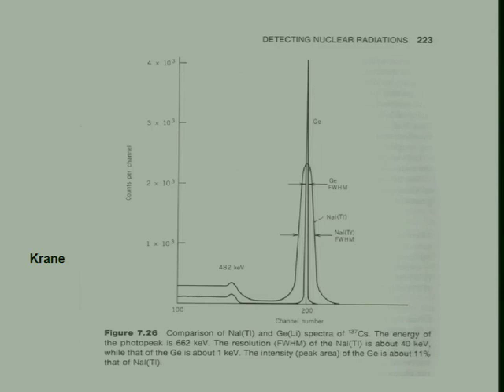And so it's the full width at half maximum there. And for sodium iodide, it might be something like 40 keV for this particular energy, which means something like 6 or 7% energy resolution at this energy. Whereas for germanium, it's much, much better. You can see the peak is much narrower, and you'll see that in a minute. And it's more like 0.1% or a few tenths of a percent for this kind of resolution.